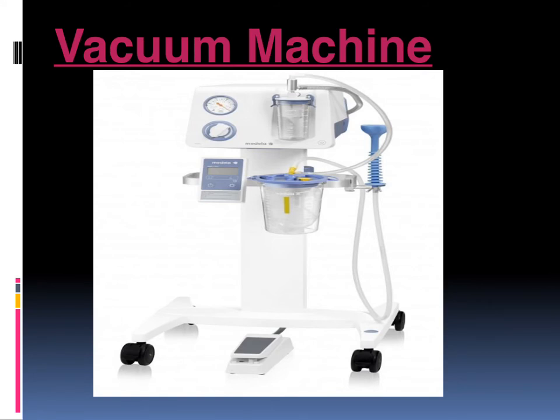You can see a vacuum machine in this slide. You can see the pedal with which you can release the suction as well as apply the suction using your leg. You can also see the tubings, the gauge, and the blue 50-size vacuum cup. Nowadays we also have disposable vacuum cups; this is a reusable silicone vacuum cup which can be autoclaved and reused.